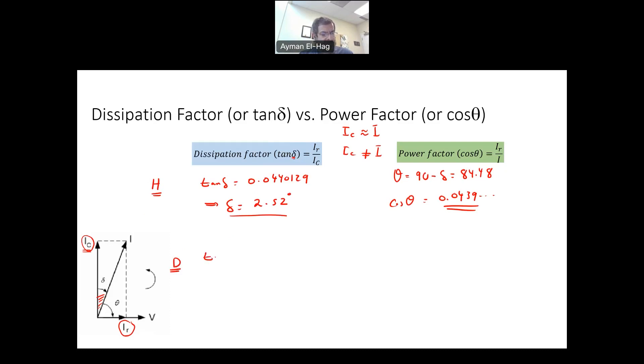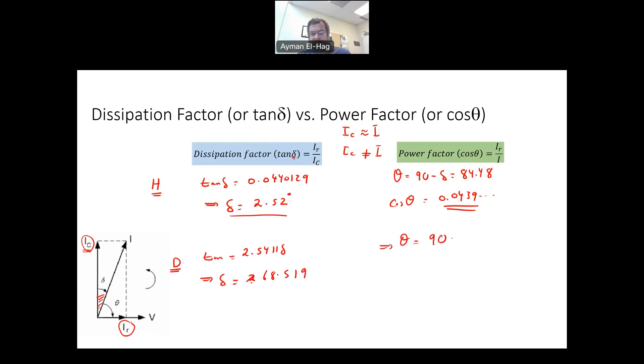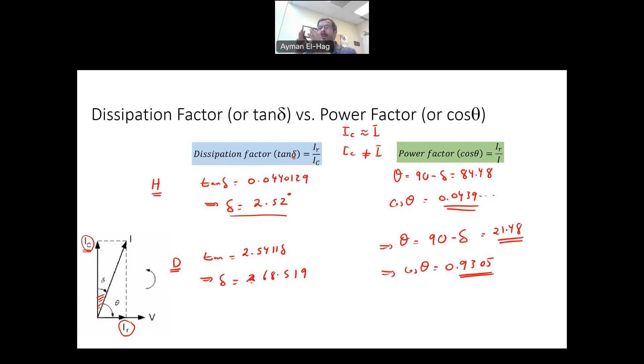On the other hand, when we have a defective insulator, tan delta equals 254%, or 2.54115. This means that delta equals 68.519 degrees. From this, theta — which is 90 minus delta — equals approximately 21.48 degrees. Then cosine theta, which is cosine of this angle, equals 0.93005, which is almost unity power factor — almost a pure resistive load. That is why when we use the words dissipation factor and power factor as synonyms, we mean only for healthy insulators. Once the insulator becomes unhealthy or defective, they are two completely different things.